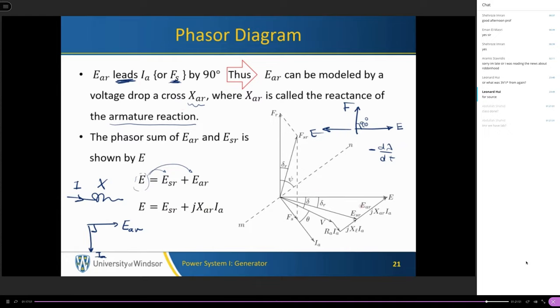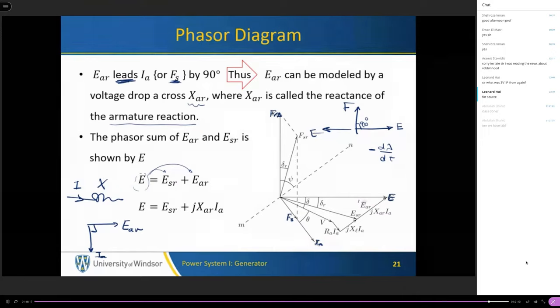Now let's look at the phasor diagram. This is E, the one induced at no load. We don't have any load. The generator is connected to the grid, everything is good, and we have this magnetic field by the rotor, FR. When we have a current, this current will generate FS. And because of this current, we have a component called EAR, the armature reaction voltage.